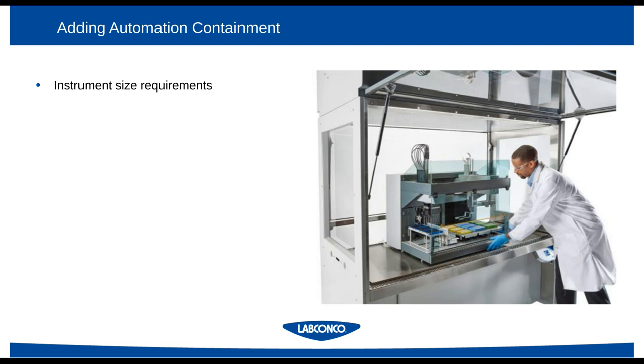Additionally, I wanted to revisit the importance of looking at the compatibility of your instrument and an enclosure, and that starts again with looking at the instrument size requirements, looking at the ergonomic requirements for operation and service. So you can see here this gentleman is loading an Evo platform, and it's easy to do so because the sash swings all the way open and provides great access to the interior. Also ensuring, again, cords, cables, and fluid lines are considered before purchasing an enclosure. With the Logic View, you don't have to worry so much about compatibilities because there is quite a bit of flexibility, but if there are unique lines involved, it's really important to consider those dimensional requirements for those tubes.